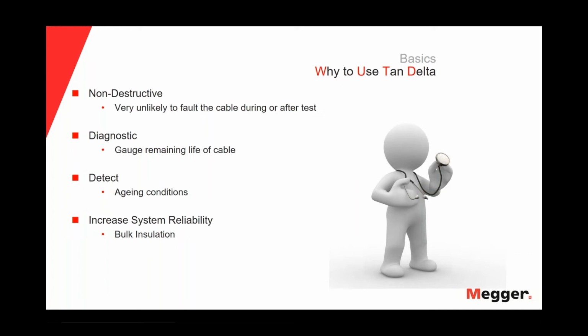And it's a diagnostic tool to measure the remaining life of the cable. The idea is to detect the aging conditions in the insulation of the cable. Of course, we use the tan delta to increase the system reliability. Okay, that is the reason we use the tan delta.